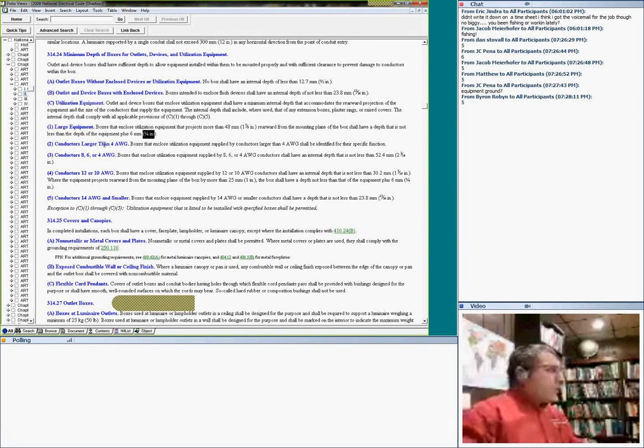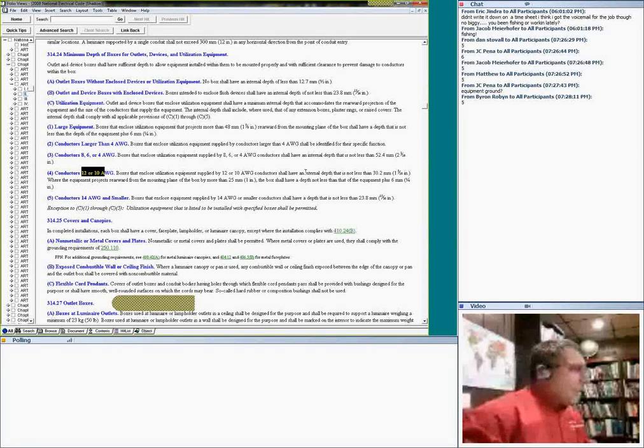Conductors larger than number 4: the equivalent of a conductor larger than number 4 shall be identified for the use. Conductors 8, 6, and 4: boxes that enclose conductors 8, 6, and 4 should not have a depth smaller than 2 and 1/16. Conductors 12 and 10: an internal depth that is not less than an inch and 3/16.